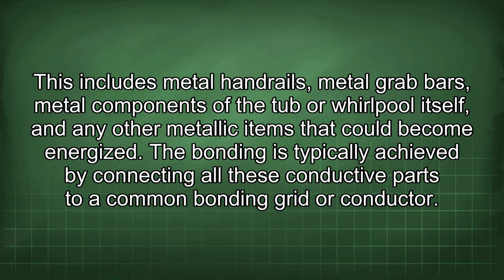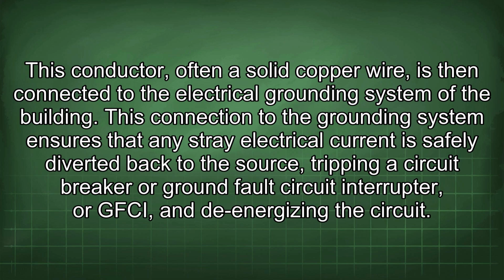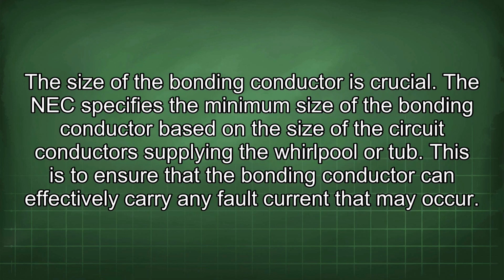that could become energized. The bonding is typically achieved by connecting all these conductive parts to a common bonding grid or conductor. This conductor, often a solid copper wire, is then connected to the electrical grounding system of the building. This connection to the grounding system ensures that any stray electrical current is safely diverted back to the source, tripping a circuit breaker or ground fault circuit interrupter, or GFCI, and de-energizing the circuit. The size of the bonding conductor is crucial. The NEC specifies the minimum size of the bonding conductor based on the size of the circuit conductors supplying the whirlpool or tub. This is to ensure that the bonding conductor can effectively carry any fault current that may occur.